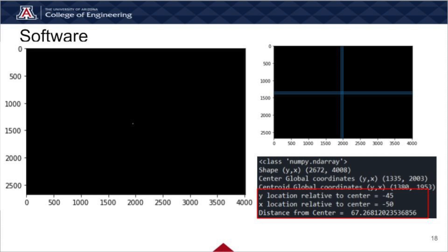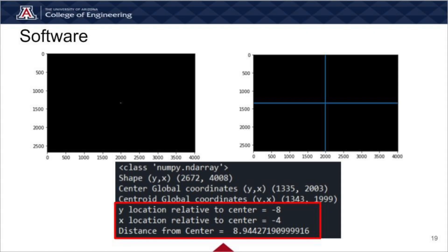The beam's initial location will vary. Using the detector and video feed, coarse adjustments can be made to bring the beam towards the center. Then an image is taken and processed by the program. In the top right image, crosshairs mark the center of the image and centroid of the beam. The returned values in the bottom right are used to determine the fine adjustments to be made by the alignment system. On the next slide, we have proceeded ahead four iterations to arrive within 15.1 pixels, indicating alignment to within 10 arcseconds.